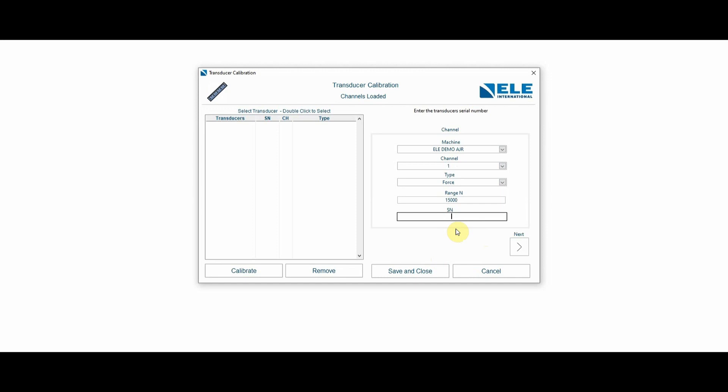Then I'm going to enter the serial number, which in this case for the transducer that I have is this one right here. This information you're going to find in the calibration certificate that comes with each one of the transducers when you open the box.